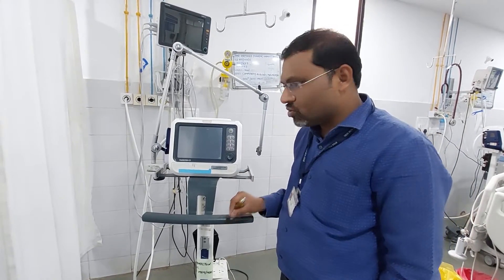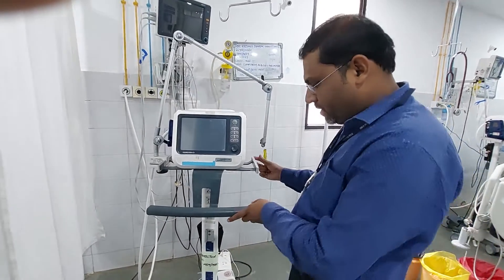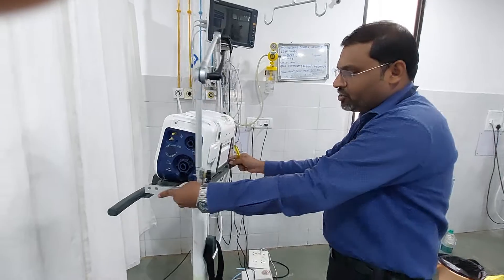So what is the average life of an O2 cell? It will depend upon use, but it should last up to one year. I will show you how to replace the O2 cell. At the back side of the machine you can observe...